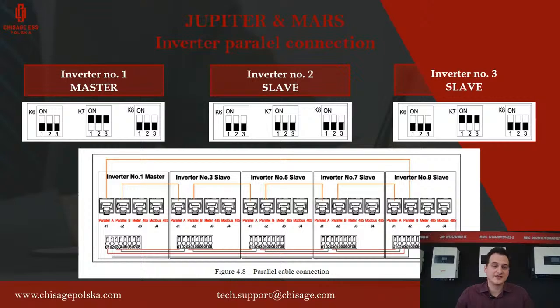For the first and the last inverter, we go with K7 on. So K7 is on, K6 and K8 are off. For all the other inverters, all three switches are off. So if we have three inverters, that means the first and third will have K7 on, and the second inverter K7 off. If we have more inverters, all between the first and the last will have all the switches off. So those are the things we have to connect, and we have to check them under our communication cover.